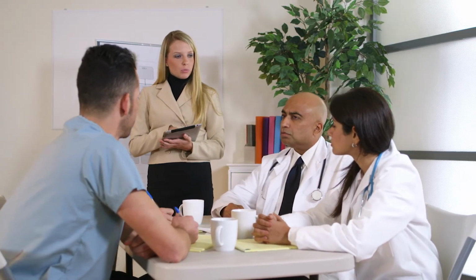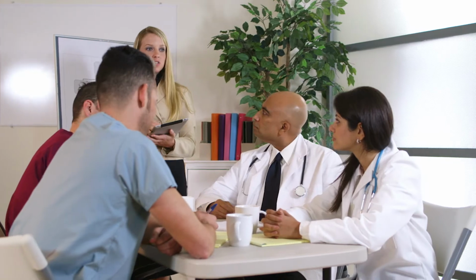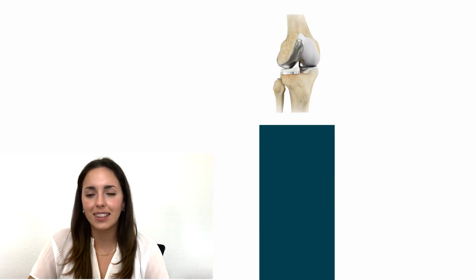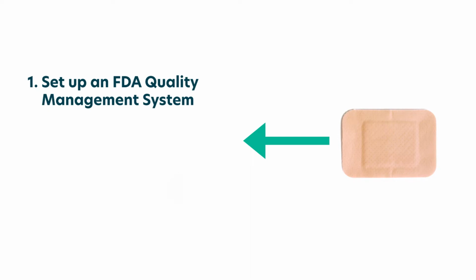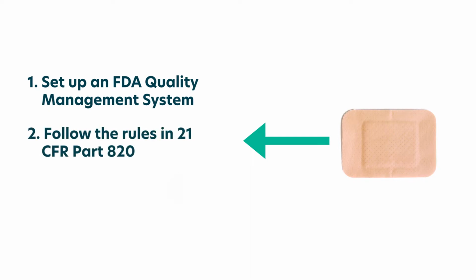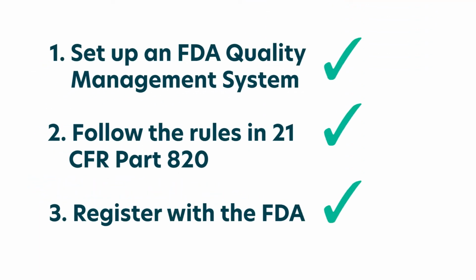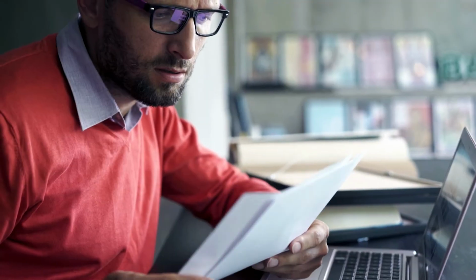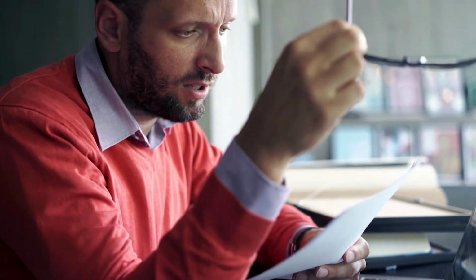Depending on your device class, you'll need to follow the FDA regulations for getting clearance. As you can imagine, they're more difficult for Class 3 devices and less tedious for Class 1. In general, for Class 1 devices, you just need to set up an FDA quality management system and follow the rules laid out by 21 CFR 820. And lastly, register with the FDA. Once you've completed all 3, you're ready to go.